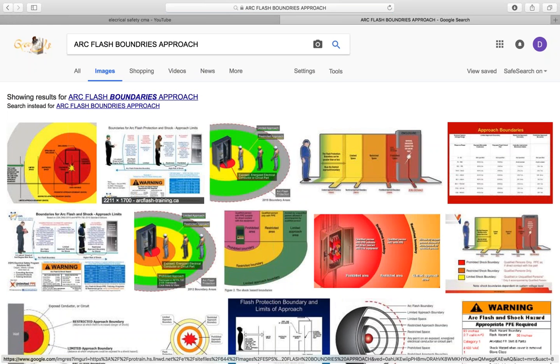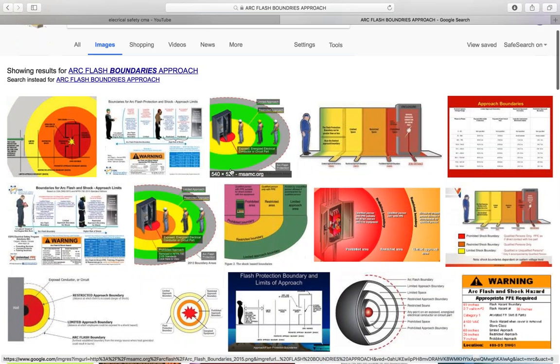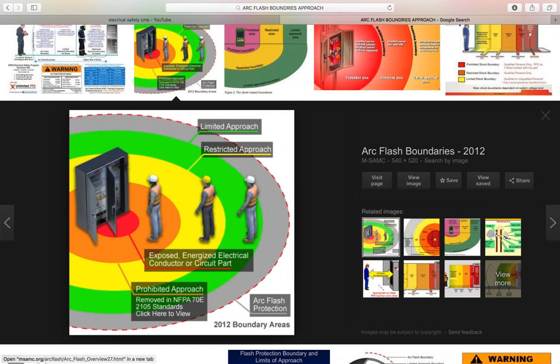Okay, so these are the approach distances. This is how they do it with arc flash. As you see, the darker the color is, red, the greater hazard we have. It starts even telling us who's prohibited in what areas, who's allowed to work in there, restricted and even limited duty, just depending on the type. And normally it's restricted by three things: the potential hazard, the level of training of the employee, and the level of PPE that they have on against resistance to arc flash. So those are usually the three things that are the most quantifiable when we're talking about approach distances to panels.